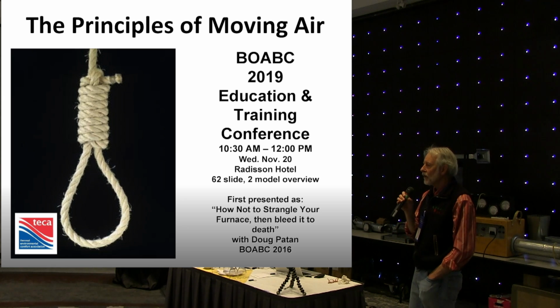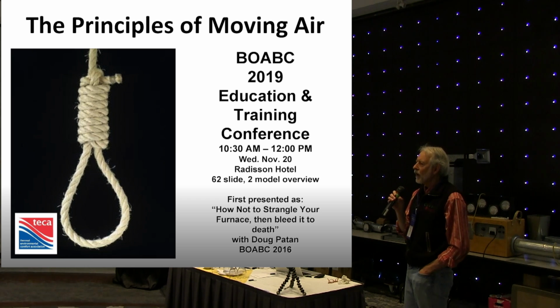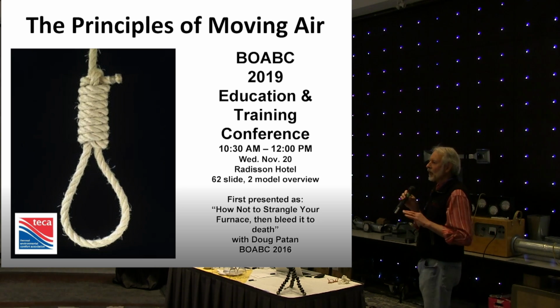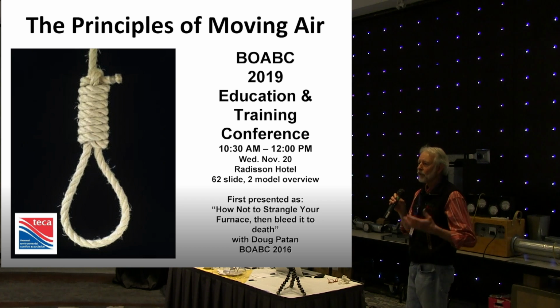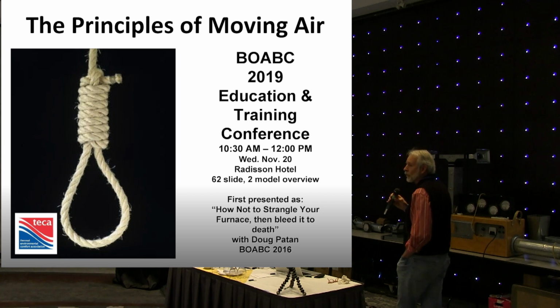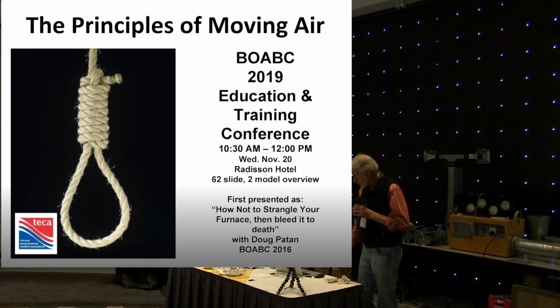The toy on the right is very complex, but we're only going to use it for one specific example, to show you the biggest single restrictor to free-flowing air in forced air systems installed in this province. Hands down, it's the filter. So please feel free to ask any questions at any time. As you probably heard from my noise this morning, I am not easily disturbed or disrupted. We'll just go through some slides, and I will stop when I can best serve your interests.